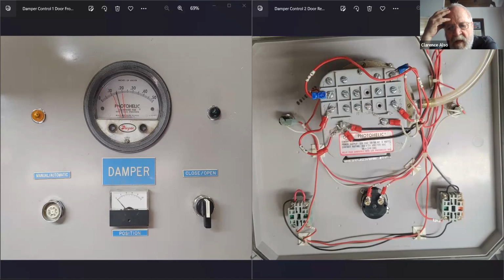Then you can see our automatic - on the left side there, that's going to be our open-close switch. You can see we've got some contacts in there, and the contacts at rest are both green, meaning they're both normally open contacts. Whenever it goes into one position or the other, closed or open, one of those green things is going to come up - that's normally open becoming closed, which gives us 110 volts going to our actuator.